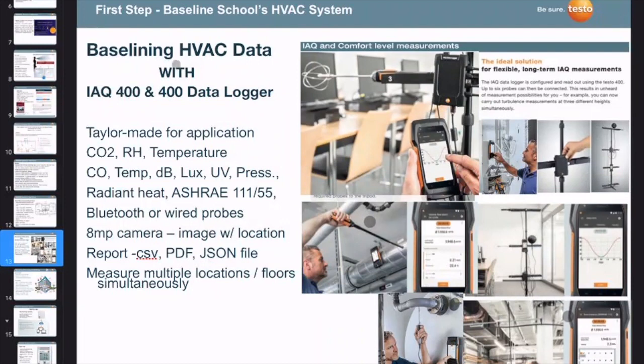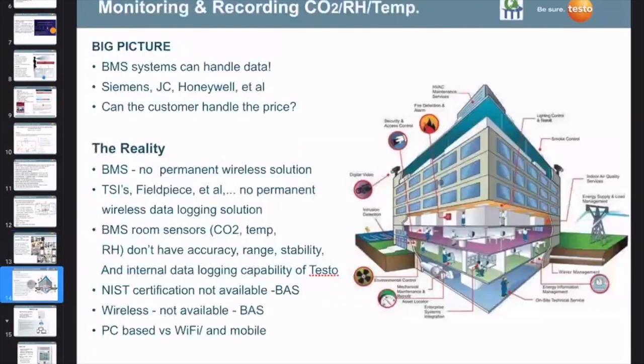And then going forward, once again, as we said, once the building has been baselined, you go into an operational sequence mode whereby the school needs to start installing the proper sensors for CO2, temperature, and humidity. And they actually mention in the document that it can be done, or should be done, by one of two methods. One, by contacting the local BMS or BAS supplier, such as Siemens, Johnson Controls, Honeywell, and others like that, to install this monitoring system, or to be provided by suppliers that manufacture sensors and data loggers like ourselves.